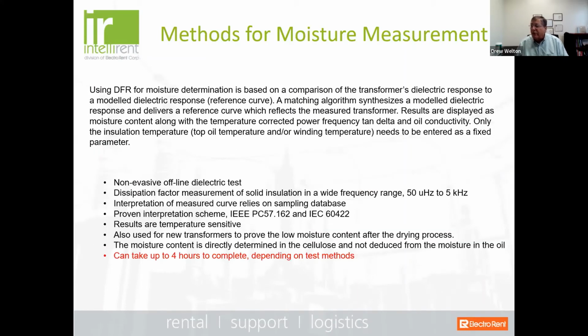But using DFR for moisture determination is based on a comparison of the transformer's dielectric response to model dielectric responses that they did under laboratory conditions. So what happens is you are measuring this wide frequency range of the dielectric response and equating the results to what was determined under laboratory conditions using a Karl Fischer titration. Under laboratory conditions, meaning that you knew the exact percentage of moisture in the insulation and could compare that to how it responded to the particular curve that's going to be a result of this test. But it is non-invasive and it is done offline.